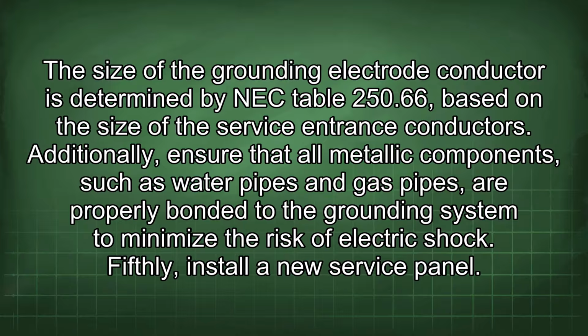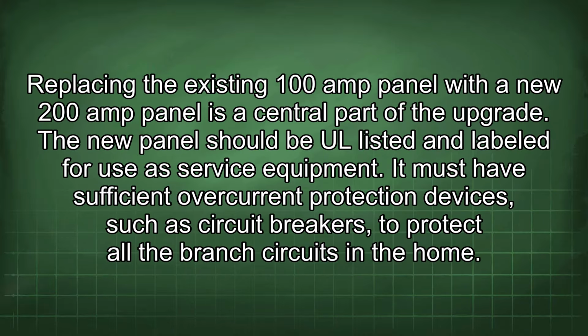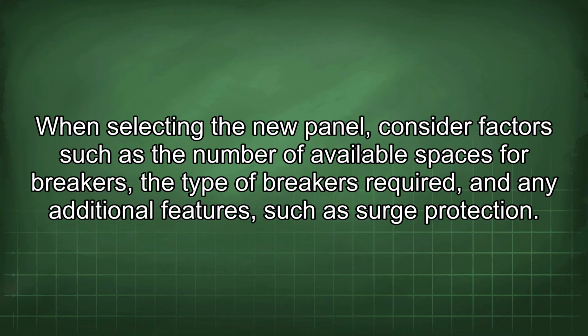Fifthly, install a new service panel. Replacing the existing 100 amp panel with a new 200 amp panel is a central part of the upgrade. The new panel should be UL listed and labeled for use as service equipment. It must have sufficient overcurrent protection devices, such as circuit breakers, to protect all the branch circuits in the home. When selecting the new panel, consider factors such as the number of available spaces for breakers, the type of breakers required, and any additional features, such as surge protection.